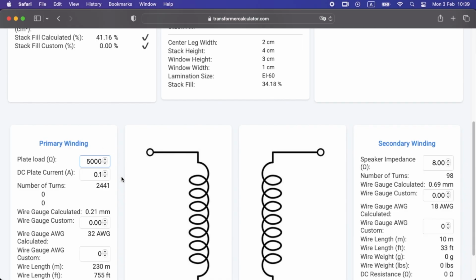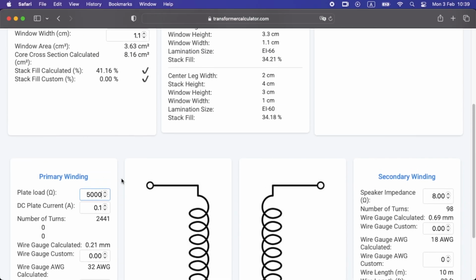But if you have too many primary turns, you run into a problem of higher leakage inductance, which diminishes the high frequency response. In order to fix that, you have to choose a different interleave system.